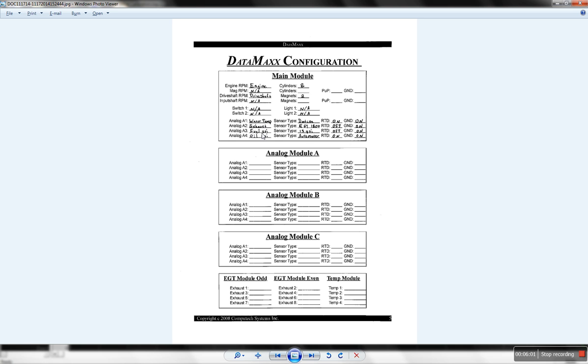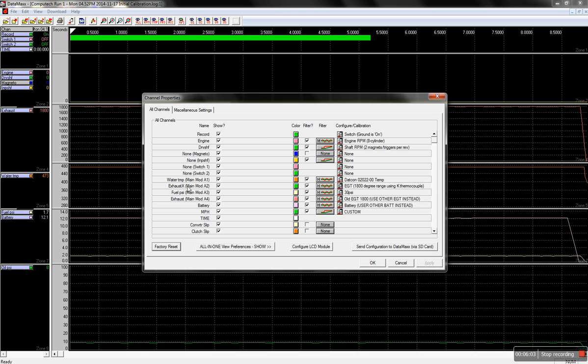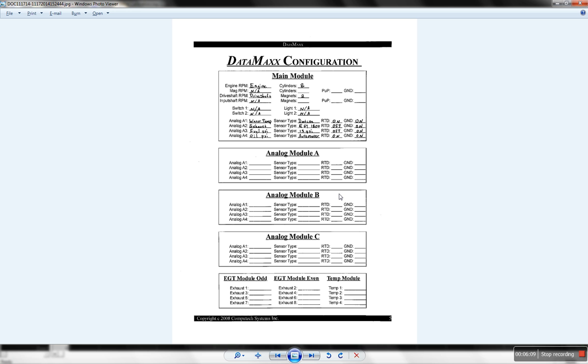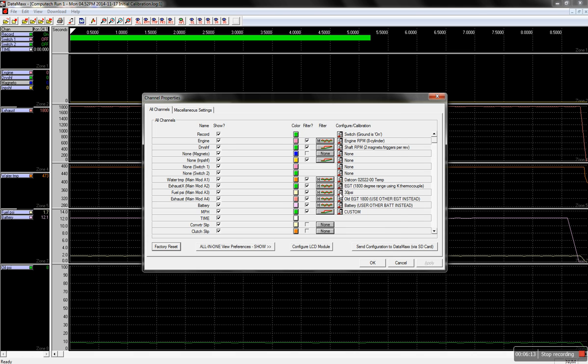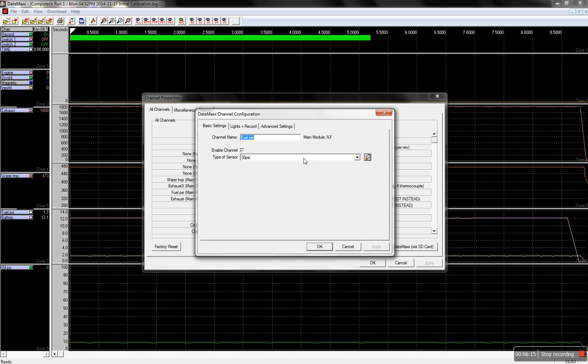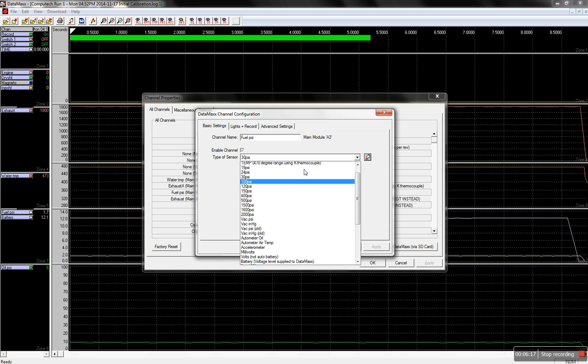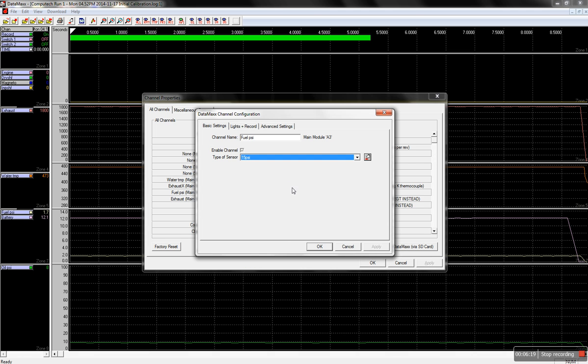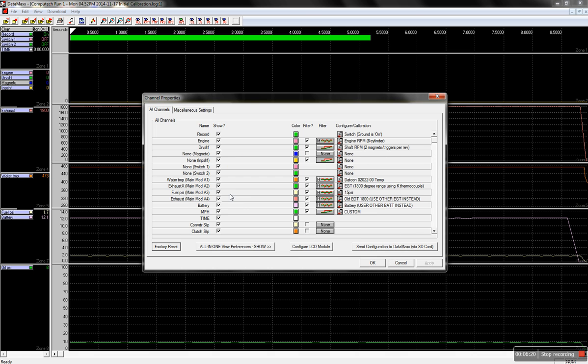We physically have fuel pressure installed there. If we look at our sheet, our calibration, we have fuel pressure. This one is labeled as a 30 psi, whereas ours is a 15 psi. So we need to make a small change there. So we're going to click on the calibration button. From the type of sensor drop-down list, we're going to go ahead and scroll up and choose 15 psi. Hit OK. Last line is main mod A4.